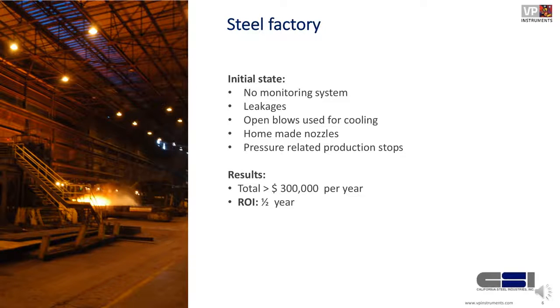This steel factory initially had no monitoring at all. They had lots of leakages, we've seen a lot of open blows used for cooling down their products, some engineers had created their own homemade nozzles, and they had a lot of pressure-related production stops. After we implemented monitoring and various steps to improve, their result was about $300,000 per year in savings. Looking at the total cost of putting in the system and metering, we saw an ROI of about half a year.